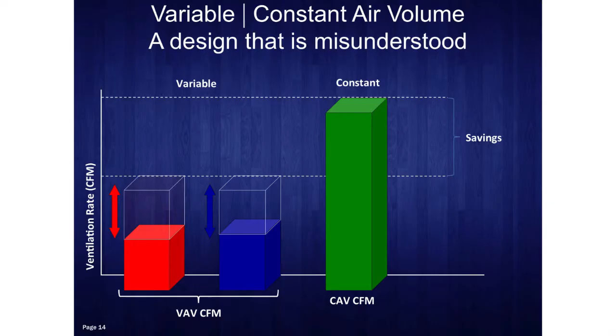Talking about raising and closing the sash, that's a dynamic change of how much air is flowing through that fume hood, right? So I caution you to say, yes, we purchased a VAV system for our building. Our hood is VAV, close your sash, okay? If you have high air change rates, this can be the scenario that you have.